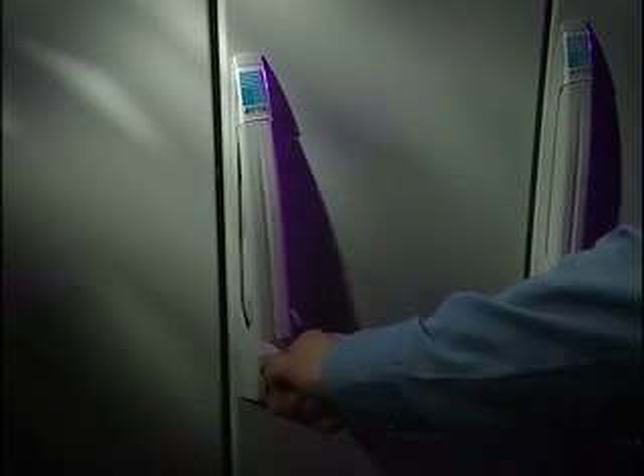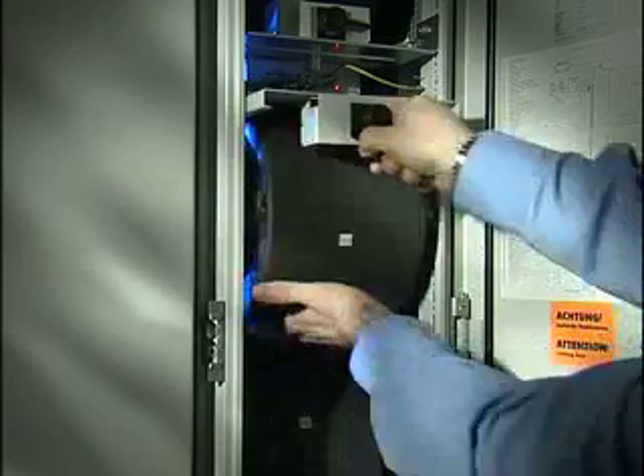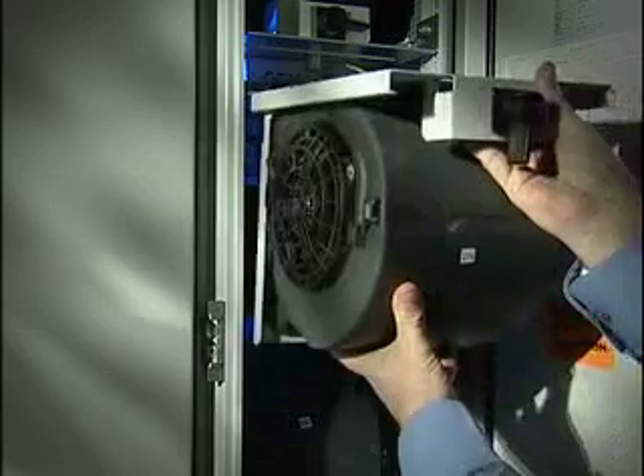The fans that push the air through the heat exchanger are fed from a single three-phase supply, two fans per phase. Therefore, in the event of a phase failure, two-thirds of your fans are still working, and the remaining fans will automatically speed up to compensate for the two that have shut down. Each fan module is hot-swappable and can be removed and replaced in seconds. Minimising the mean time to repair and mean time between failure was one of the key design considerations for LCP Plus.